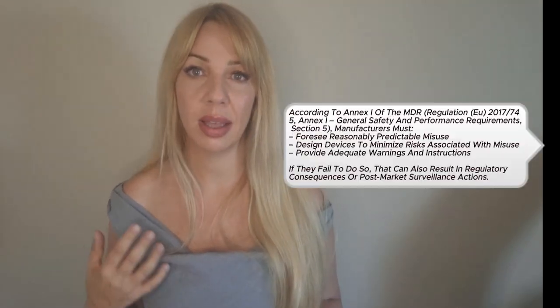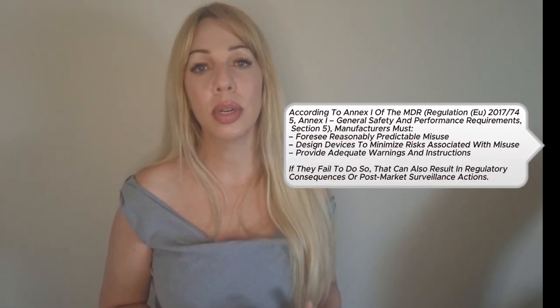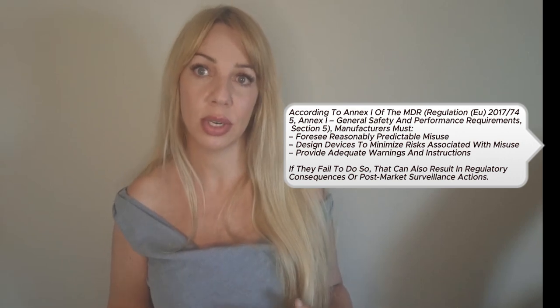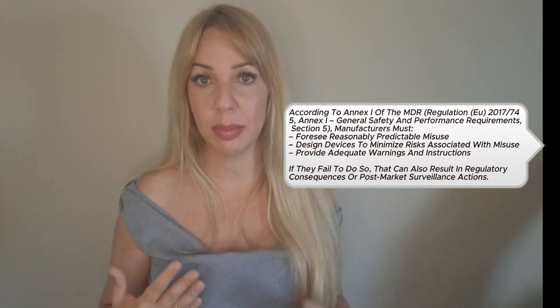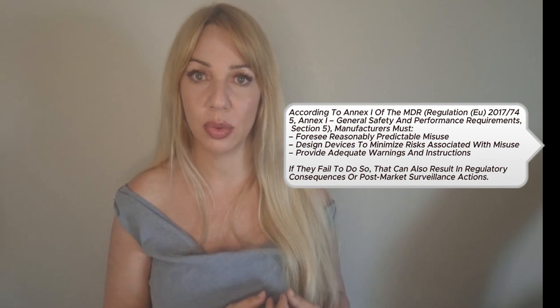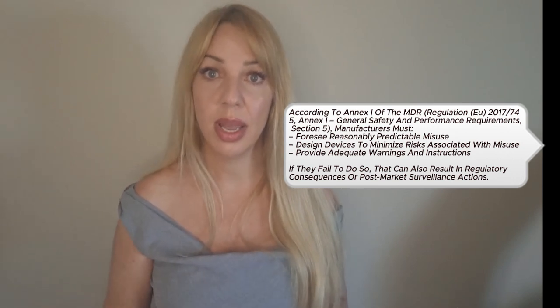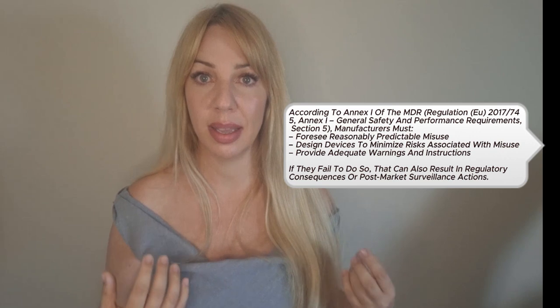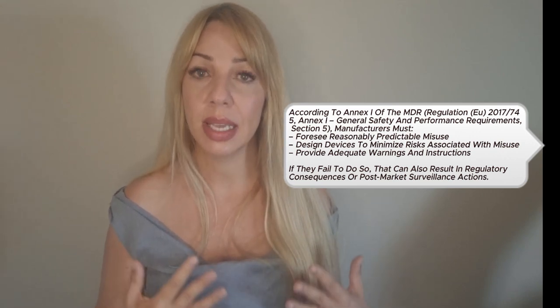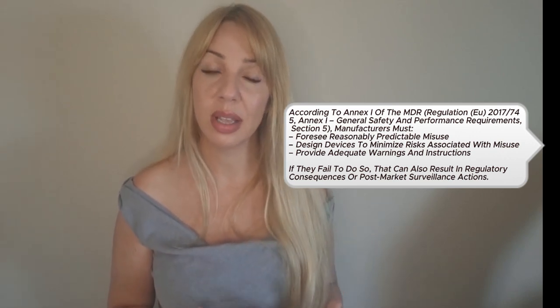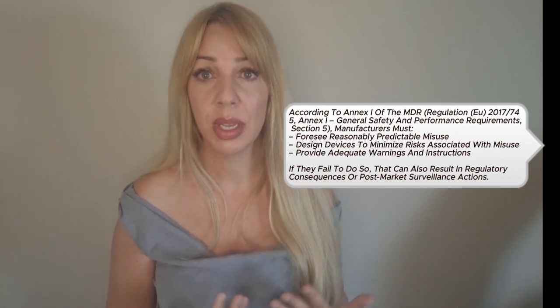But it's not only users who have responsibilities. According to Annex I of the MDR, manufacturers must foresee reasonably predictable misuse, design devices to minimize risks associated with misuse, and provide adequate warnings and instructions. If they fail to do so, that can also result in regulatory consequences or post-market surveillance actions. So what's the takeaway? Always verify the device type, its intended purpose, and its CE marked use. Never assume that only a marking makes a device suitable for injection.